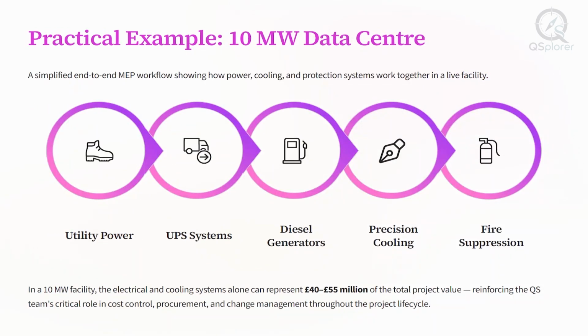Let's look at a simplified example of how the MEP systems work together in a 10 megawatt data center. Everything starts with the incoming utility power supplied by the electrical network. This power first passes through the transformers and then into the UPS system, which provides instant backup power during any interruption. If the utility supply fails for a longer duration, diesel generators automatically start and take over the load, ensuring continuous operation. Meanwhile, precision cooling systems continuously remove the heat generated by the servers, maintaining the ideal operating temperature. Throughout the facility, fire detection and clean agent suppression systems protect the valuable IT equipment without causing water damage.